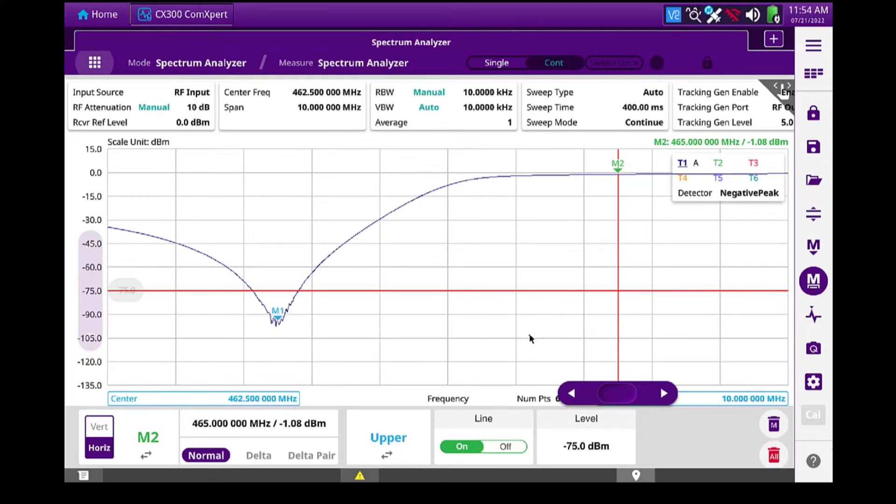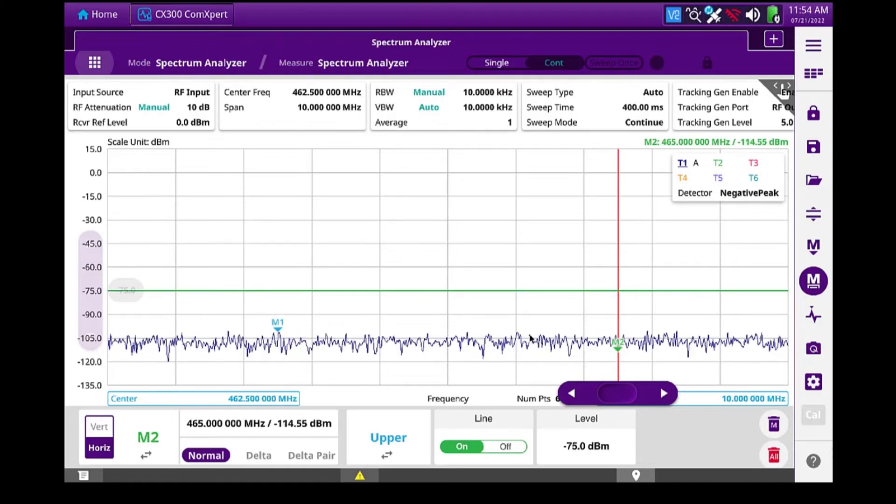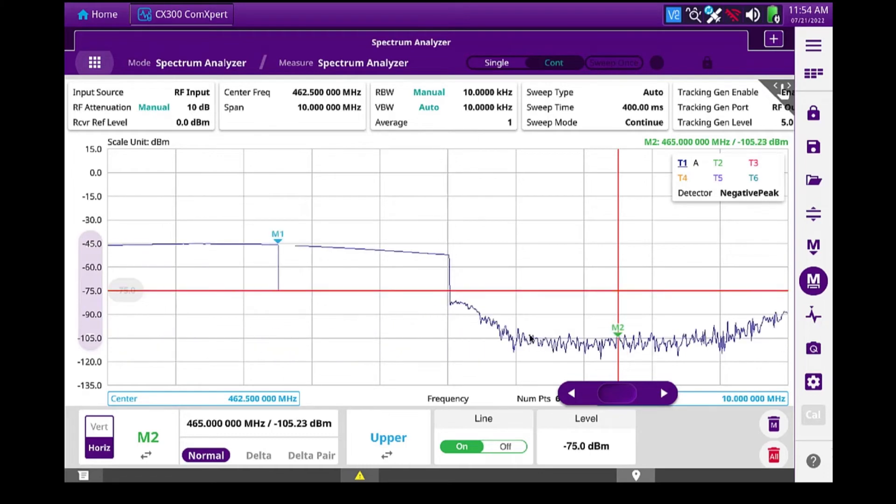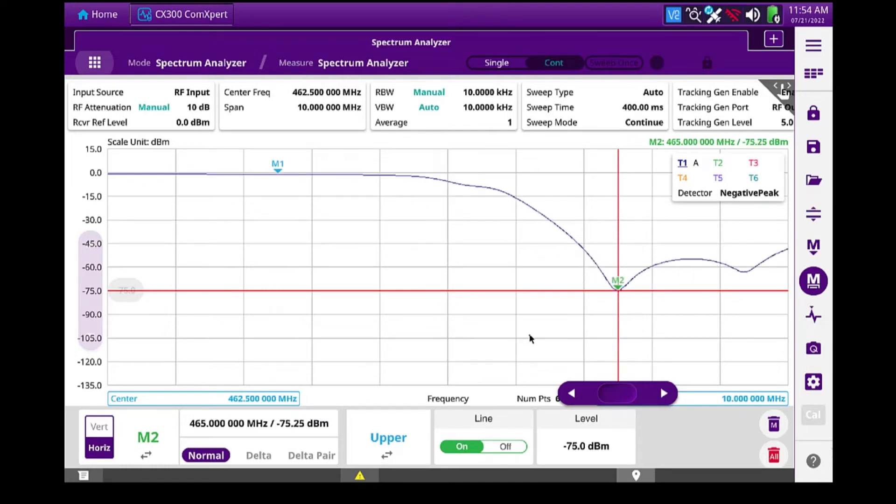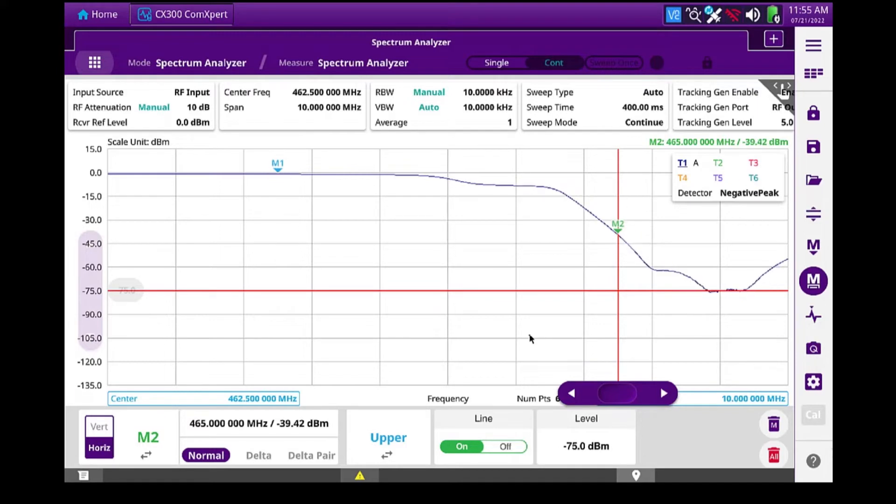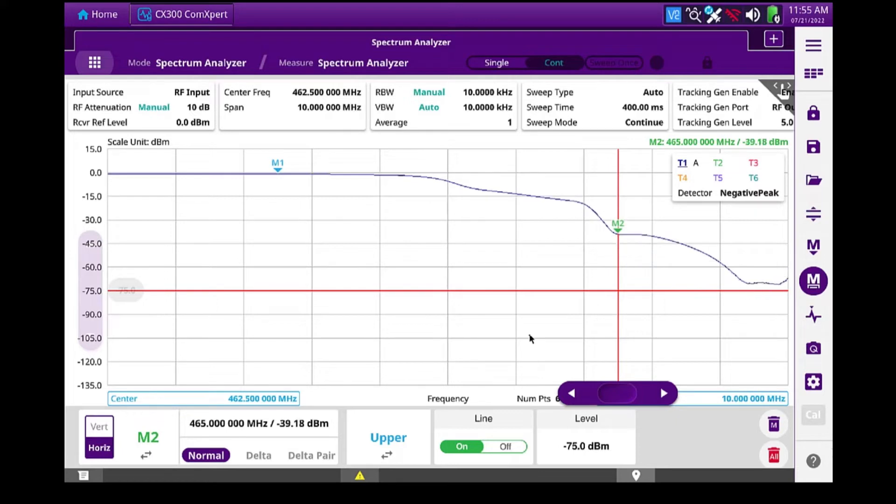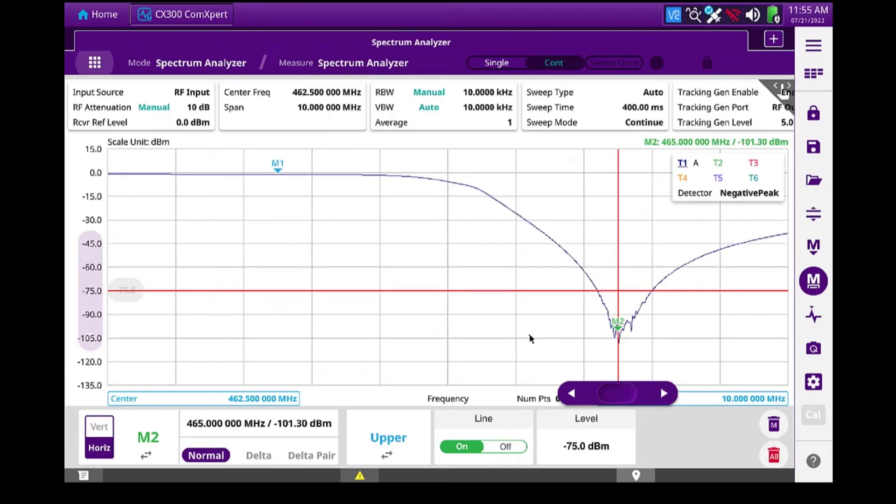So now I'm going to move my cable from the high side to the low side. And I'm going to swap my 50 ohm termination. And there it is. So let's tune on it some as well. So I've changed all three poles. I want to bring this one back to the marker. Next pole. And the third. Okay.